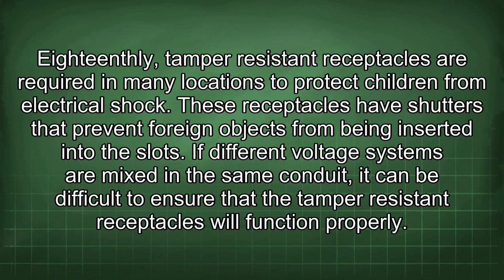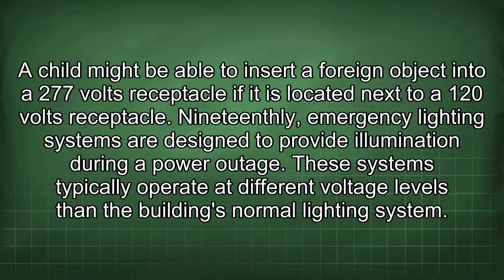These receptacles have shutters that prevent foreign objects from being inserted into the slots. If different voltage systems are mixed in the same conduit, it can be difficult to ensure that the tamper-resistant receptacles will function properly. A child might be able to insert a foreign object into a 277 volts receptacle if it is located next to a 120 volts receptacle.